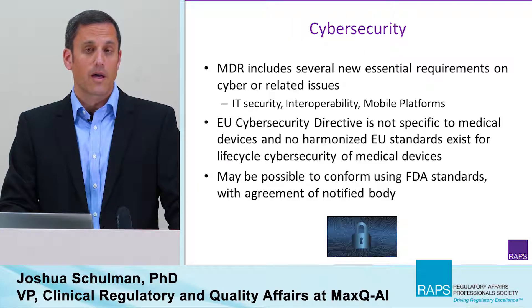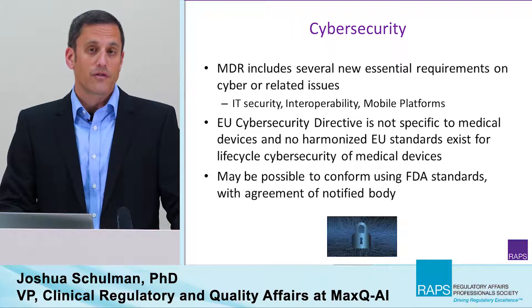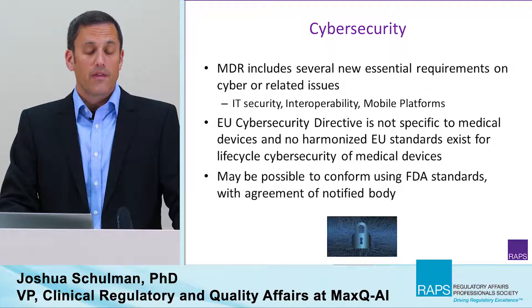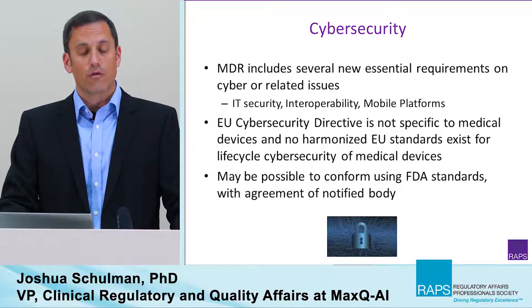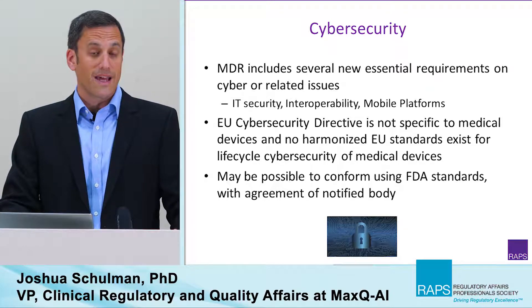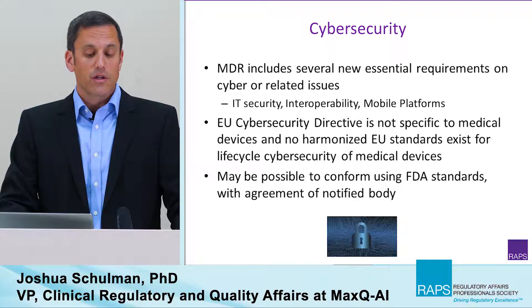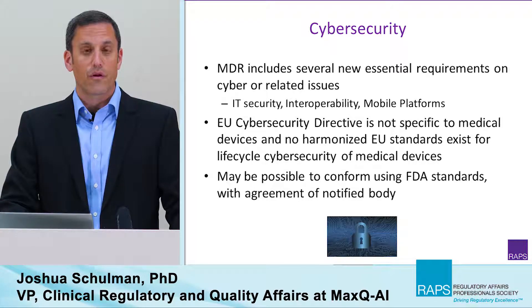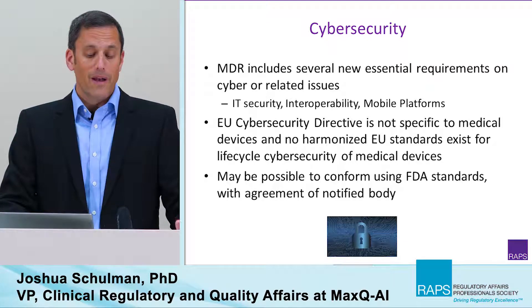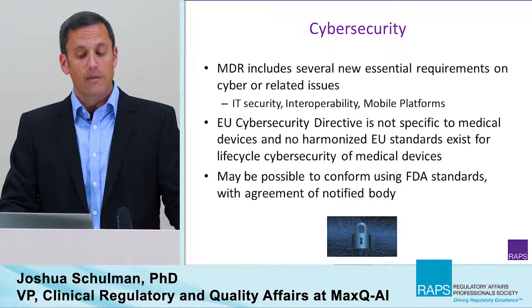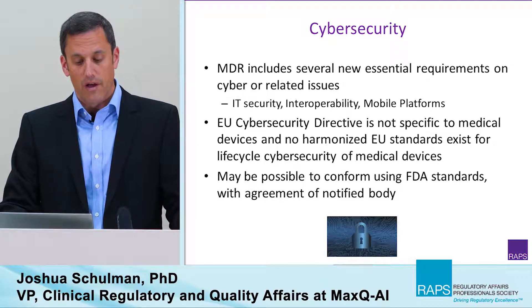An additional factor that comes up in the development of software devices in general and AI devices in particular is cybersecurity. The MDR includes several new essential requirements on cyber issues or related issues, for example IT security, interoperability, and mobile platforms. However, the EU cybersecurity directive is not specific to medical devices, and there's no harmonized EU standard for lifecycle cybersecurity for medical devices in the EU. Therefore, what many manufacturers do is they adopt the FDA standards with agreement of their notified body.